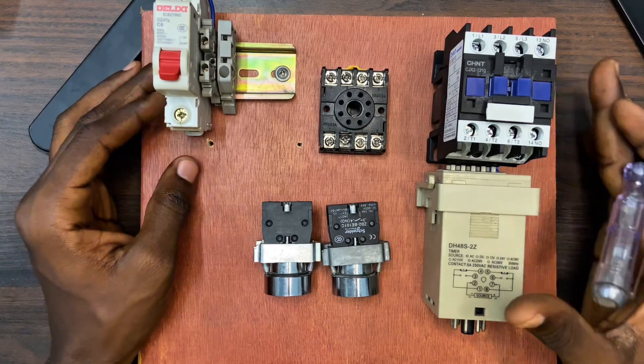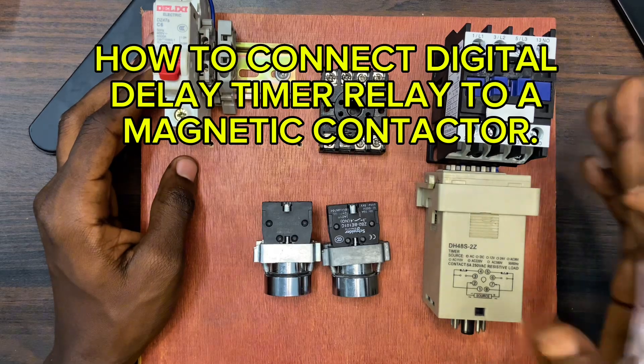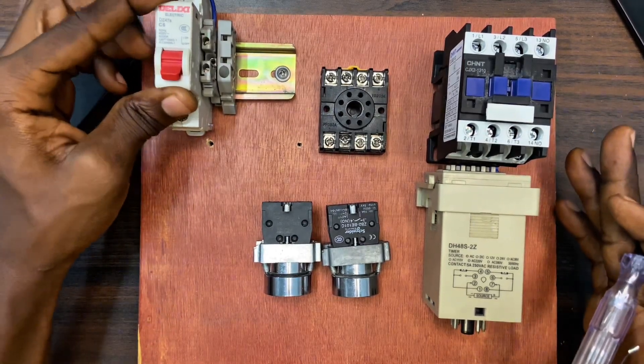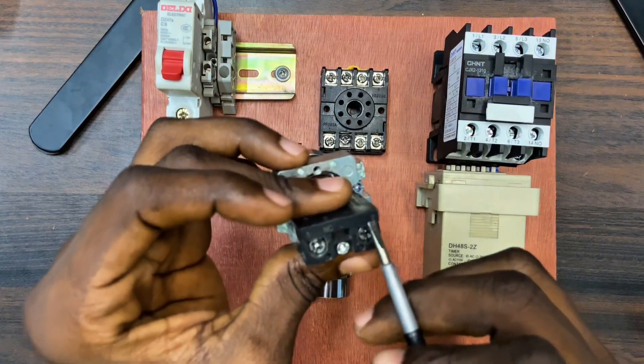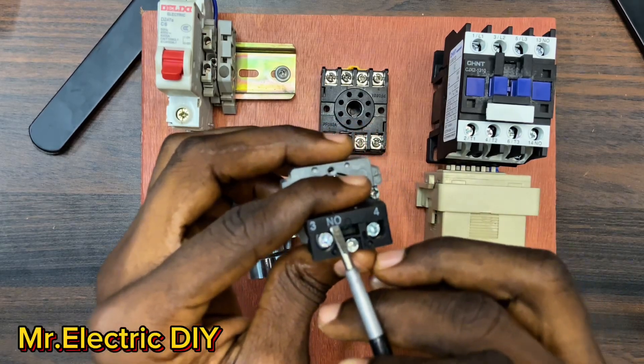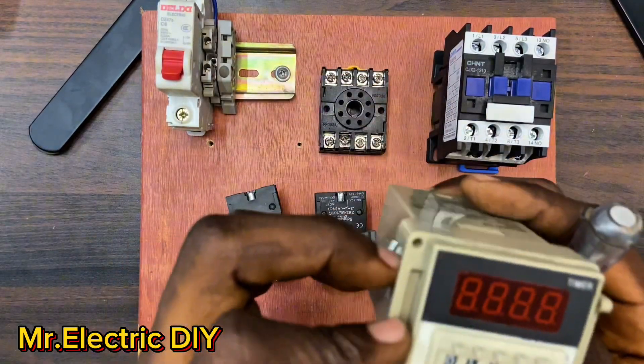Hello guys, welcome back to this channel. This video is about how to connect a digital delay timer relay to a magnetic contactor. I have my single pole circuit breaker here. These are my push buttons - we have the stop, that is number one and number two, normally closed (NC). This is the start, number three and number four, normally open (NO). This is the coil of the digital delay timer, and over here is the base or the socket.